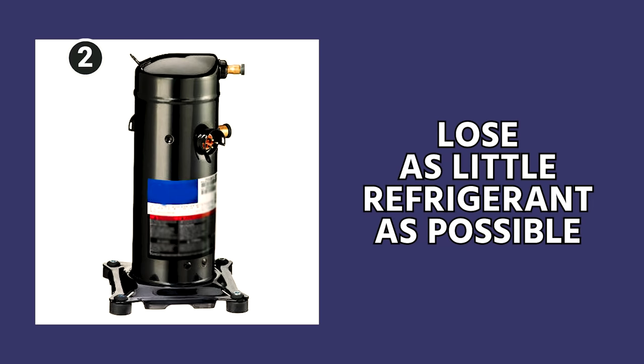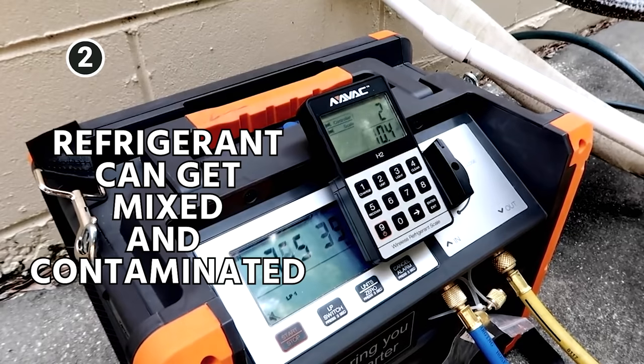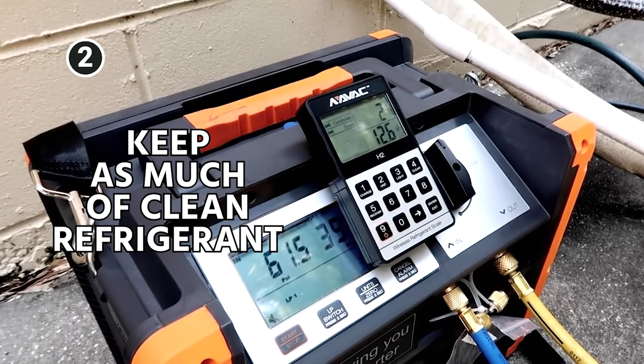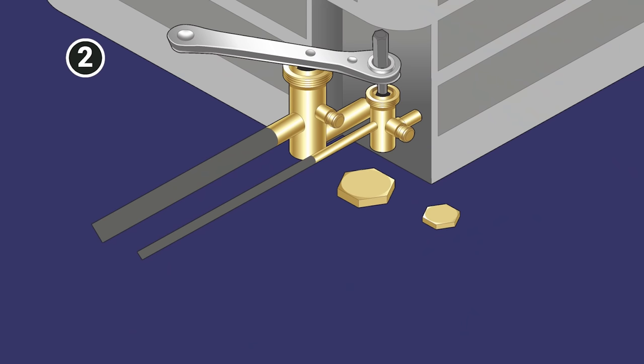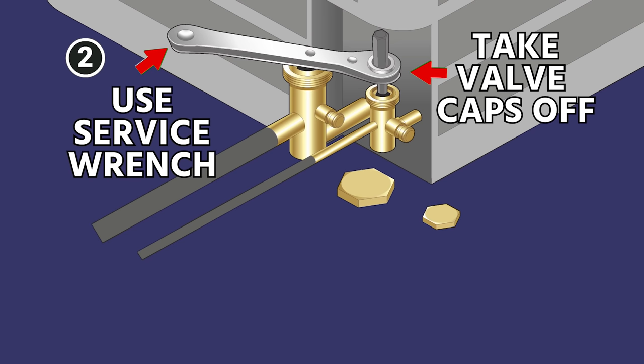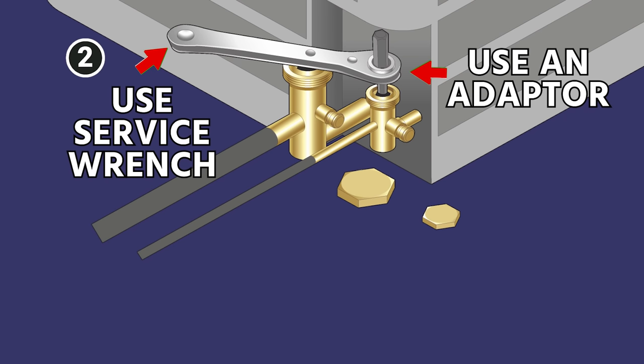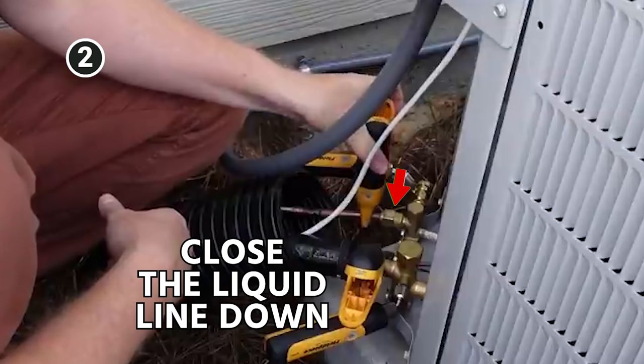So that way you lose as little refrigerant as possible. Because as you know, even when you put some into the recovery machine, that last little bit of refrigerant can easily get mixed and contaminated. So you really want to keep as much of that clean refrigerant in the system as possible for cost savings. What you're going to do is take your valve caps off, use your service wrench and usually just use a little adapter or another hex key, and close the liquid line down.